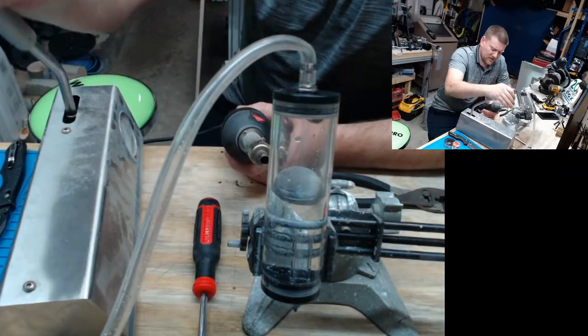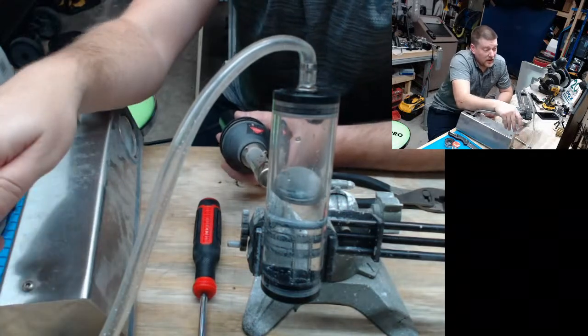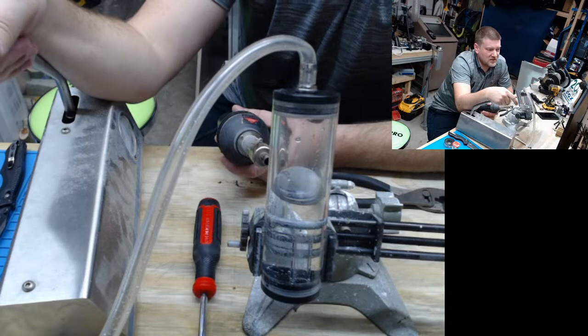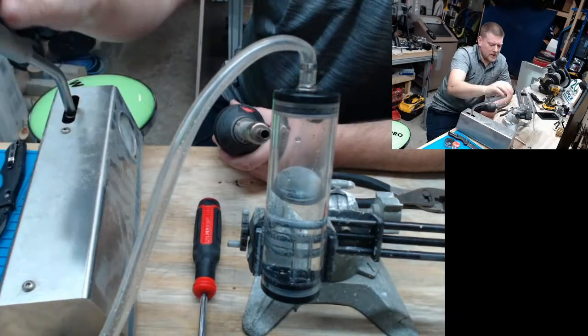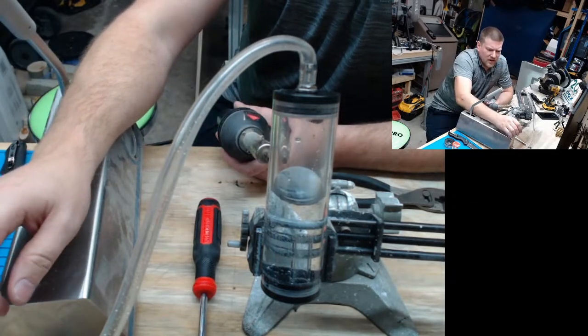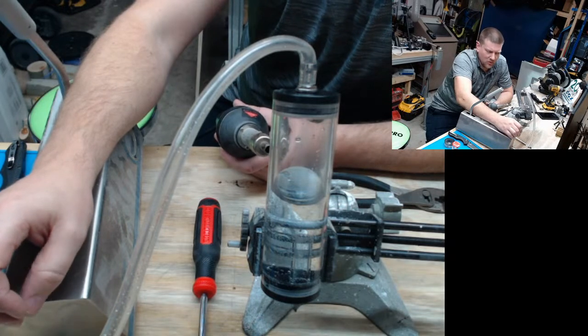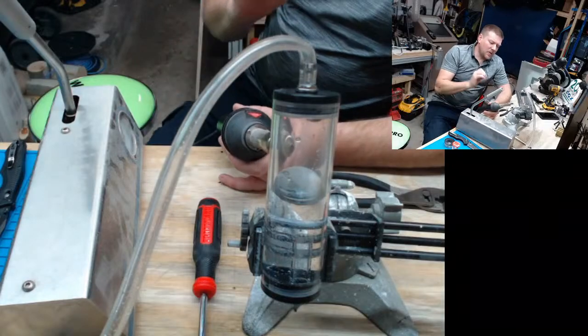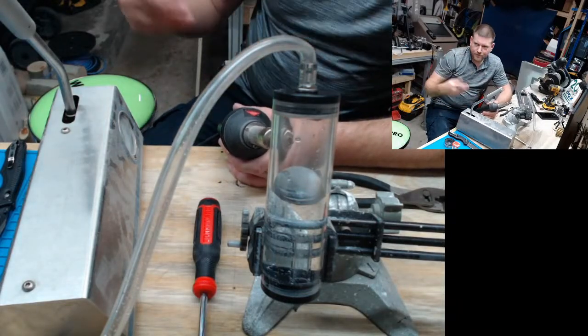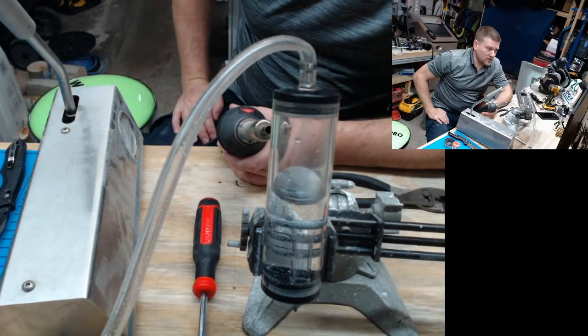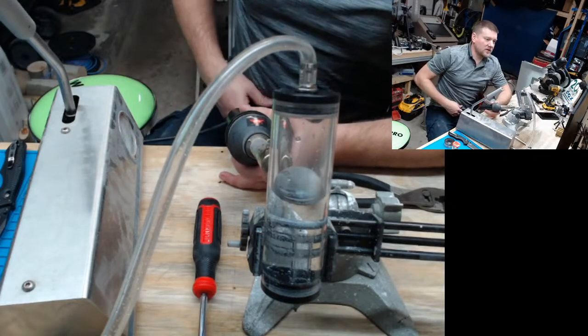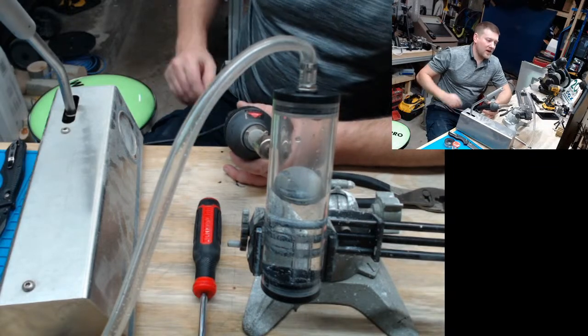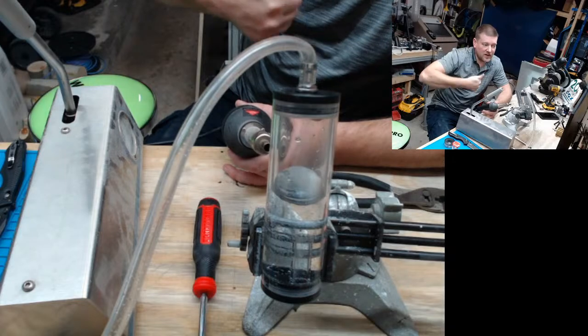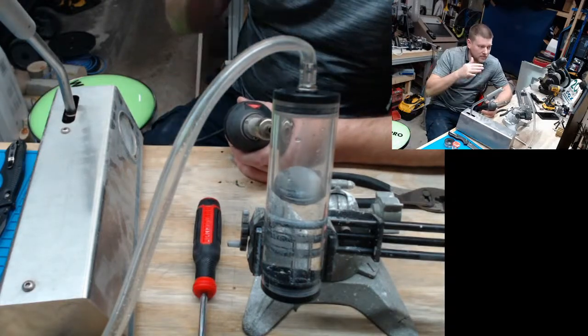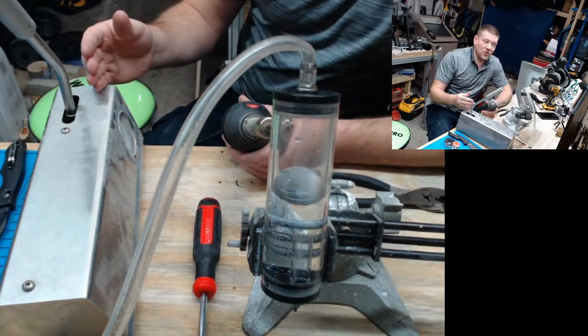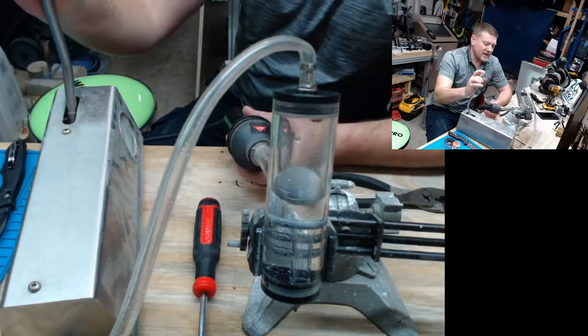So in Biomed, we fix sterilizers, and sterilizers normally run at what, 275 degrees F, if I remember right. And the thing about that is sterilizers run at a hotter temperature than boiling water. So water gets up to its maximum temperature at 100 degrees, and then it boils, and that's as hot as it gets. Okay, so if you want water to get hotter than 100 degrees, you have to apply pressure, and as you add pressure, you're allowing steam to get hotter than 100 degrees. So just steam out in room air is going to be 100 degrees, but steam under pressure can be way hotter. This, what we're doing here, is the inverse of that.